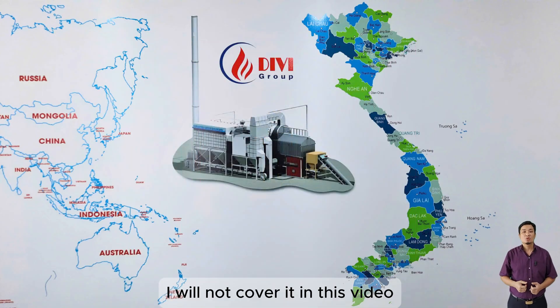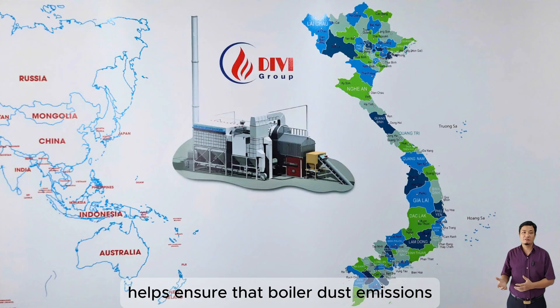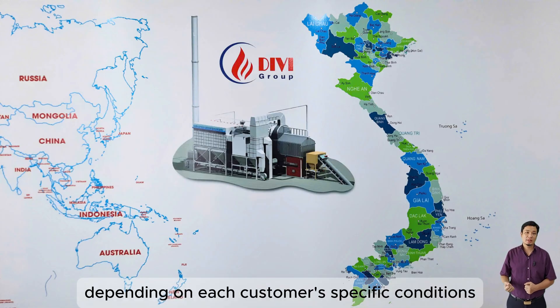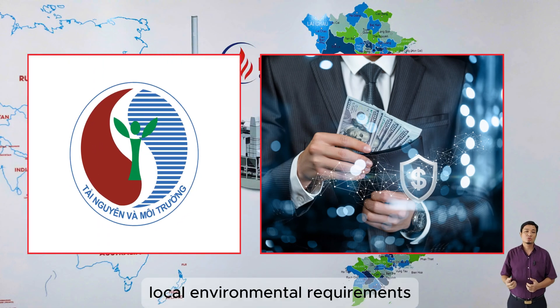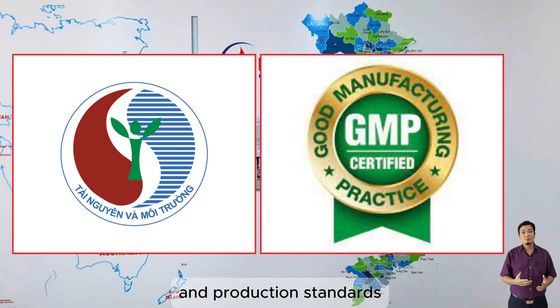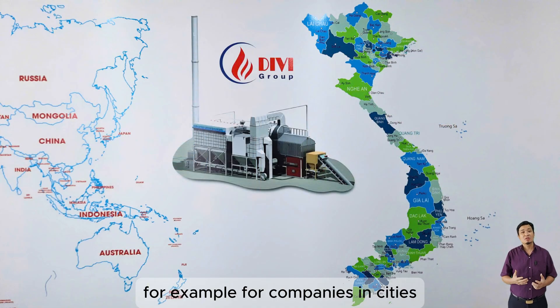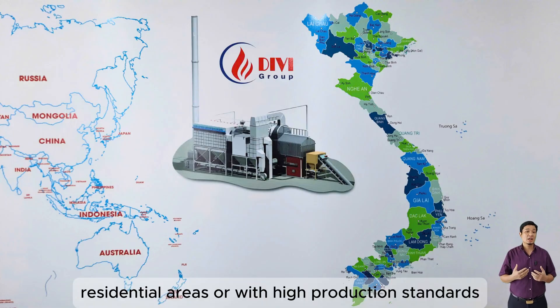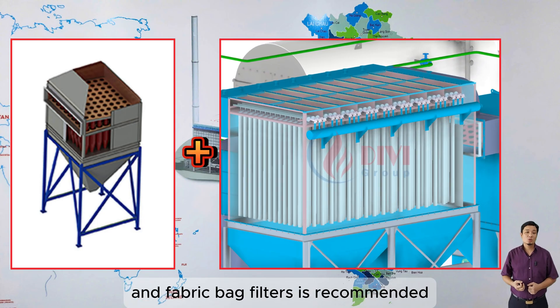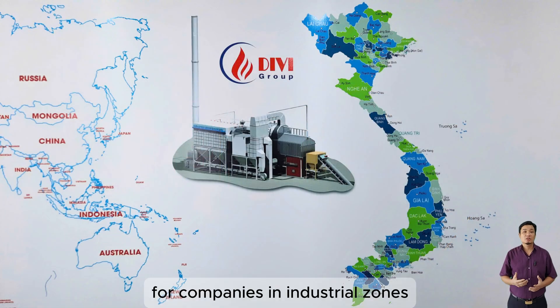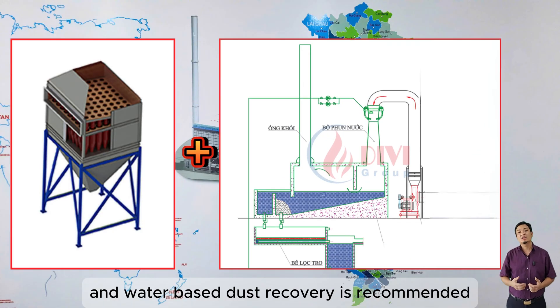In practice, combining these methods helps ensure that boiler dust emissions meet environmental standards. Depending on each customer's specific conditions such as space, finances, local environmental requirements, and production standards, different dust recovery systems may be combined. For example, for companies in cities, residential areas, or with high production standards, a combination of multi-cyclones and fabric bag filters is recommended. For companies in industrial zones, a combination of multi-cyclones and water-based dust recovery is recommended.